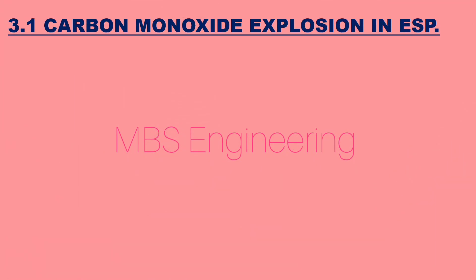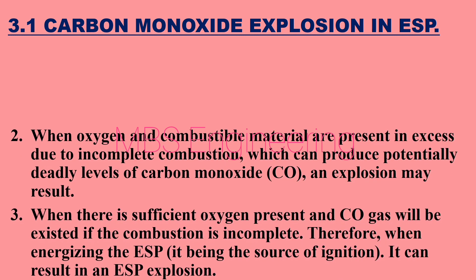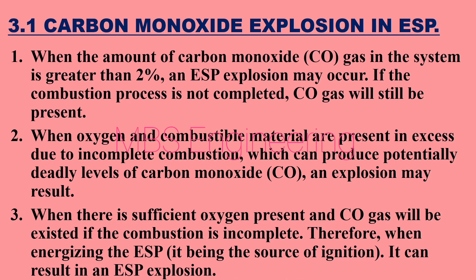Next, we will look at carbon monoxide explosions in the ESP. Point 1: When the amount of carbon monoxide (CO) gas in the system is greater than 2%, an ESP explosion may occur. If the combustion process is not completed, CO gas will still be present. Point 2: When oxygen and combustible material are present in excess due to incomplete combustion, which can produce potentially deadly levels of CO, an explosion may result.